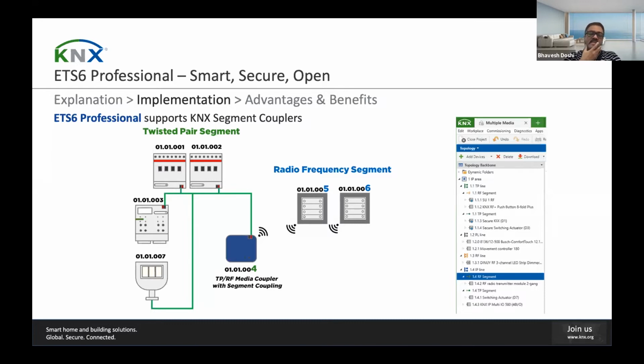While with ETS6 and support of segment coupling, the installer can simply add the segment coupler whenever on the line 1.1 and simply add the devices without the need to unmount them first in order to reprogram them. That means that the installers will not only save significant time from device wiring task, but also from the project editing task in ETS.